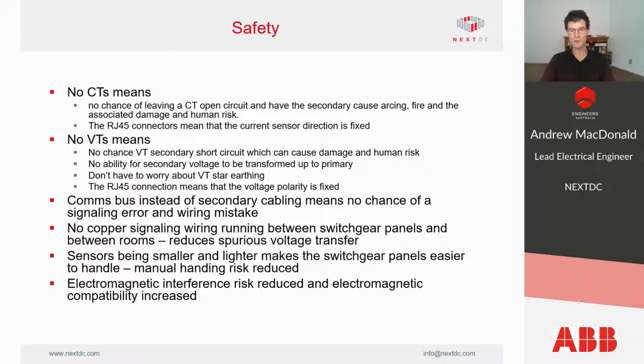No voltage transformers means there's no chance of a VT secondary short circuit, which can cause damage and the associated human risk, including explosion of the switchboard. There's no ability for the secondary voltage on the VT to be transformed up to the primary in case work's been happening on the primary side in either bus or line. We don't have to worry about VT star earthing and what configuration it needs to be in to work with a particular protection scheme. And also the RJ45 connection means that the voltage polarity is fixed.